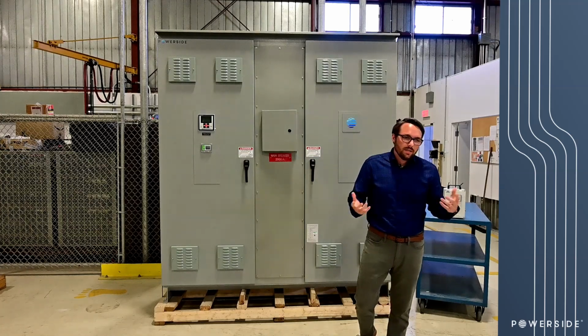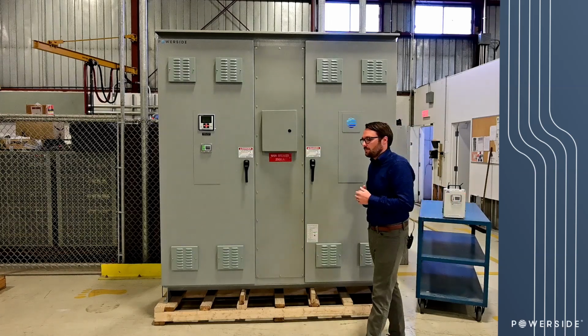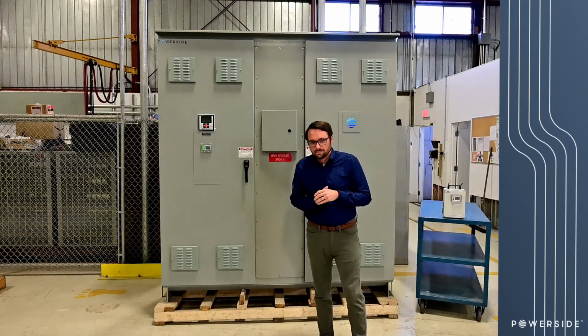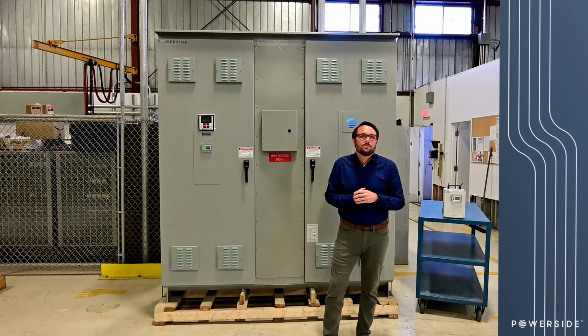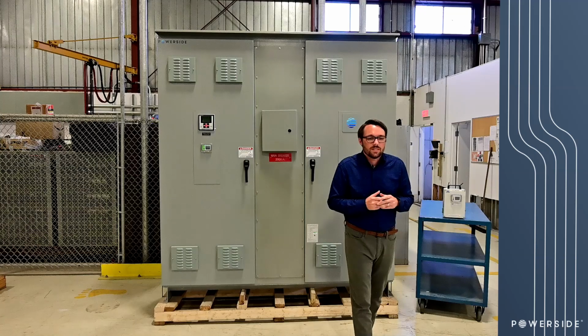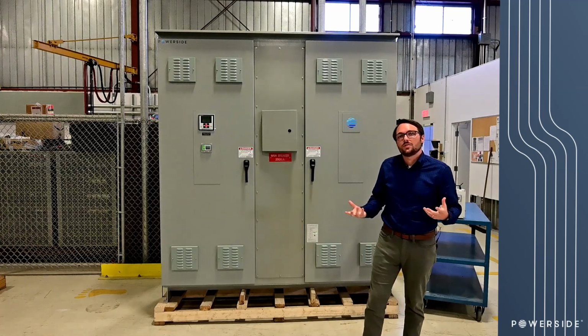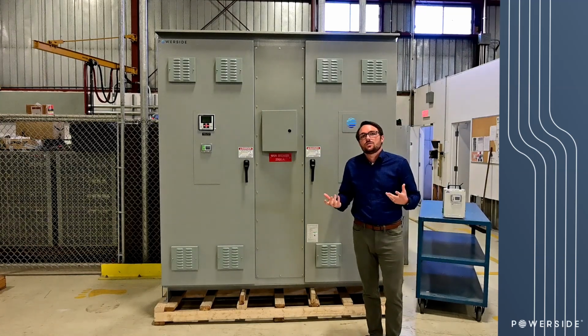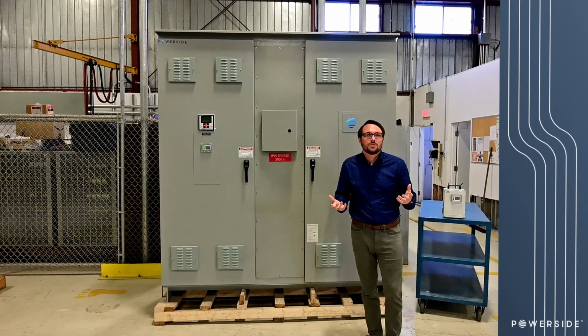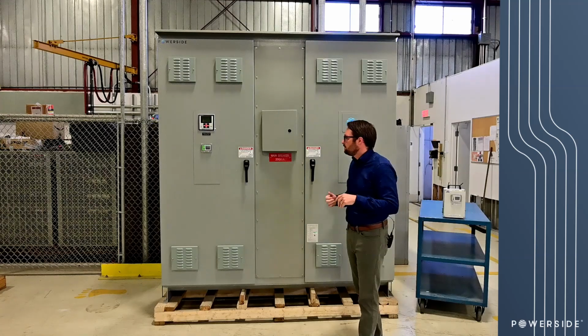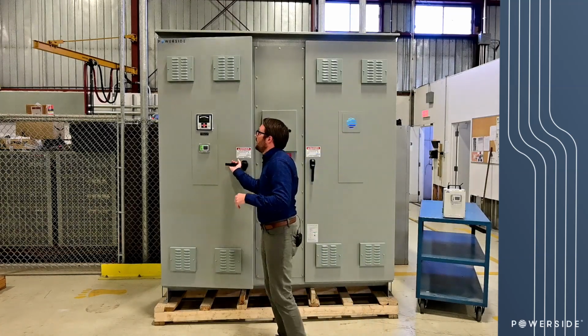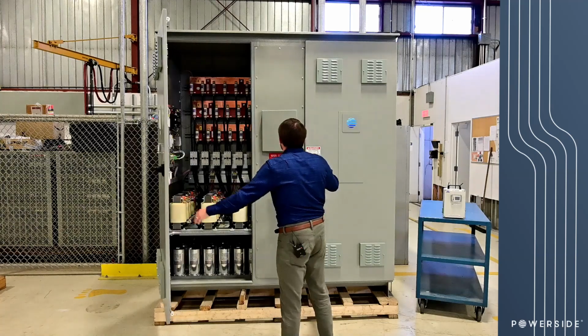So when we realized that a lot of the capacitor banks that they had on site previously had failed, this certainly started to make sense because we saw contactors that were burnt up, capacitors that had failed, fuses that were blown, etc. And so the dynamic load profile that we were seeing from this customer led us to develop what is somewhat of a unique and custom solution for this customer. And I'll share with you a little bit about it now.